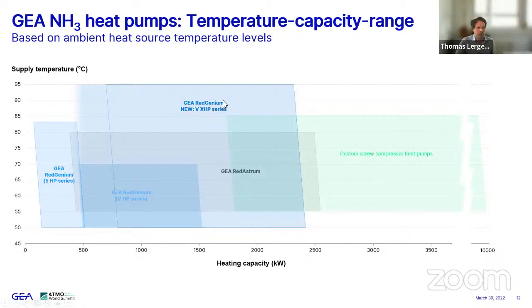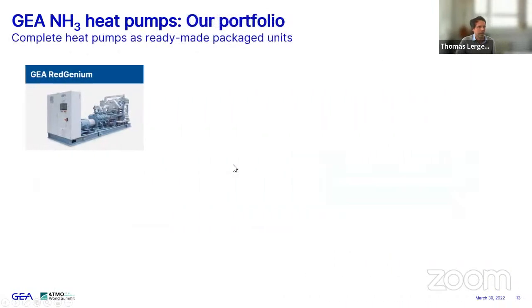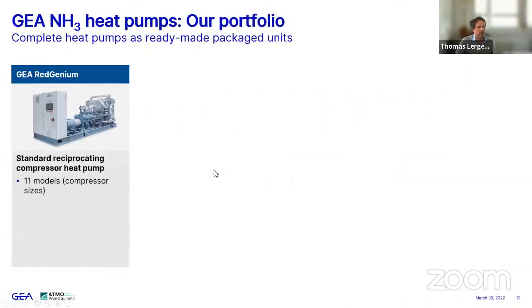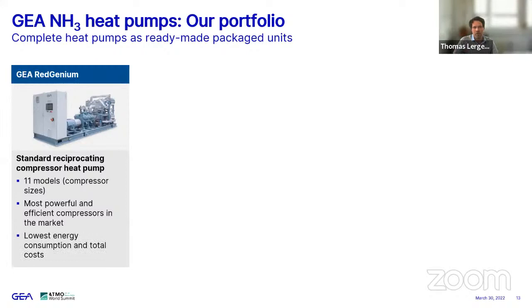If we're looking at this RedGenium model, this is our standard compressor heat pump. It looks like this. It spans altogether 11 models. So there are different reciprocating compressors included, totaling to a number of 11. They are the most powerful, efficient compressors in the market, and therefore also allow for lowest energy consumption, lowest total cost, because your energy consumption, your energy costs, they have a very, very large effect on your total cost.